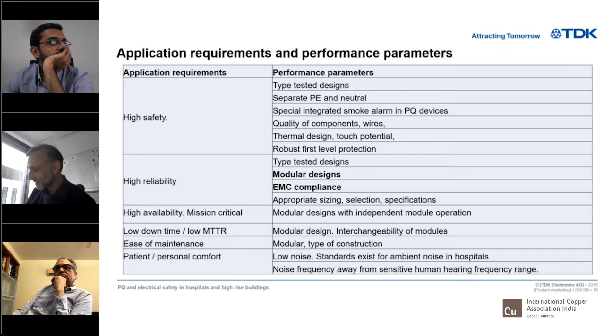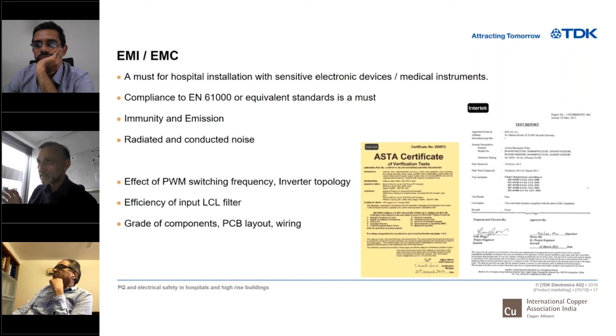It's not only the level of noise, but also at what frequency you create the noise. This is EMI/EMC. Any equipment installed in a hospital or high-rise building should have EN 61000 or equivalent certification, meaning it's immune from external noise and will not create emission that affects other equipment. These are two key aspects: immunity and emission, from both radiated and conducted noise.